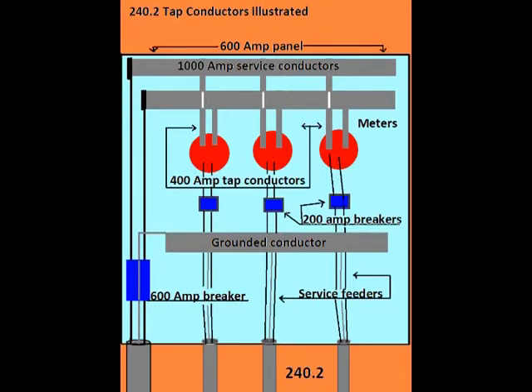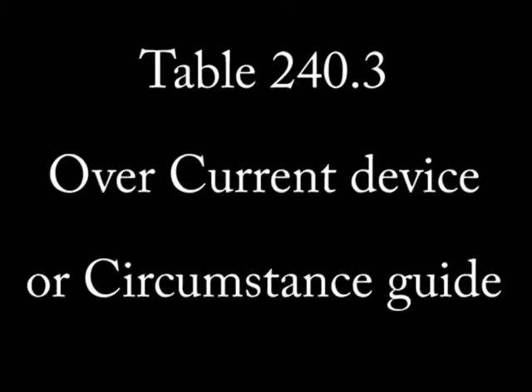If a fault should occur that exceeds 200 amps, the tap conductors will be protected by the 200 amp sub-panel breaker and the main 600 amp breaker will continue to supply the other services.